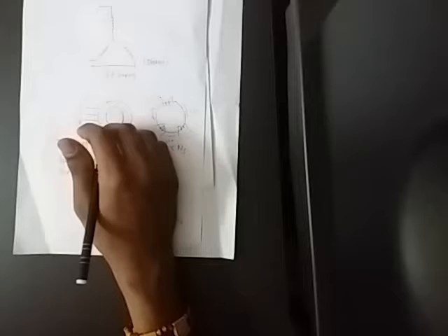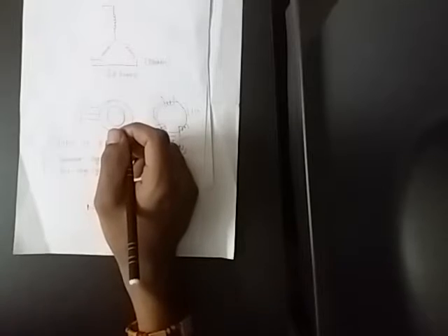Now we discuss the working of the three-phase induction motor. The working of the three-phase induction motor is very simple. The stator is wound with a three-phase balanced winding and excited by a three-phase balanced supply. So the stator field rotates at a speed called the synchronous speed. The maximum speed of an induction motor, or any motor, is the synchronous speed.